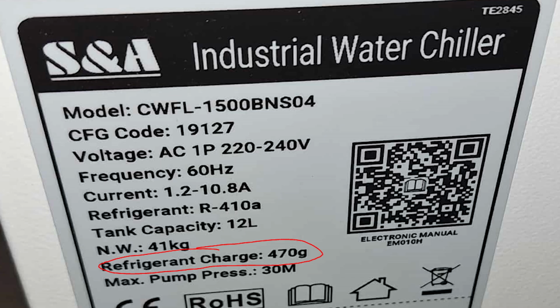First we'll look at the backplate nameplate on the back of the chiller itself. I highly recommend using this rather than a manual or some other source on the internet, because from what I've noticed there are a lot of discrepancies between manuals and other information online. But the actual charge amount of R410A the unit will hold is always on the nameplate, and it's very specific to the model you have. It's very important to only put in the amount of refrigerant listed on the backplate, because doing more or less could easily damage your unit.